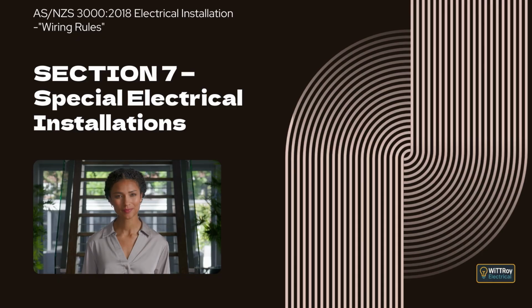Clause 7.9.4 Other electrical installations. This clause explains that electrical installations associated with electric vehicle charging, other than those specifically covered, must be protected by a separate RCD of the appropriate type and rating, ensuring protection of all live conductors and safe operation of the charging system. That brings us to the end of Section 7, Special Electrical Installations.